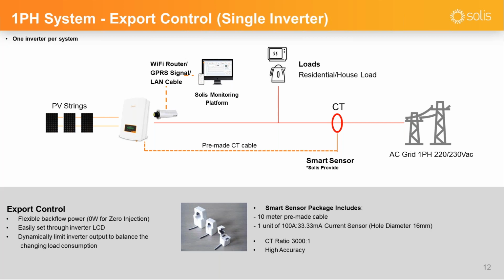So if you have any requirements like a limited injection scenario, you can also set the backflow power maybe like 1 kilowatt or 2 kilowatt. That depends on your setting in the inverter. And then the smart sensor package, you can order separately from Solis, and it will come with a 10 meters pre-made cable for the connection between the CT and the inverter, and also another unit of the 100 amp current sensor. And that sensor has a hole diameter of 16 millimeter, which is suitable for most residential installations. It's a very high accuracy smart sensor as well.